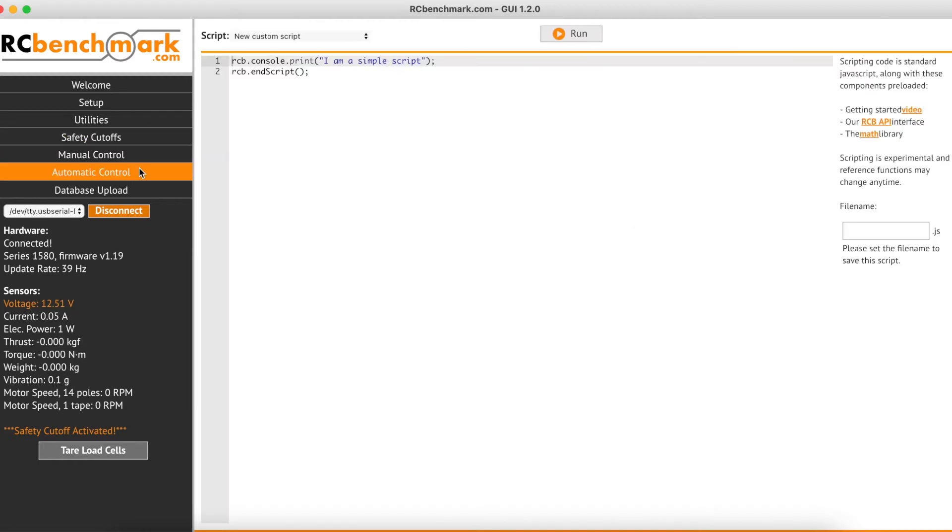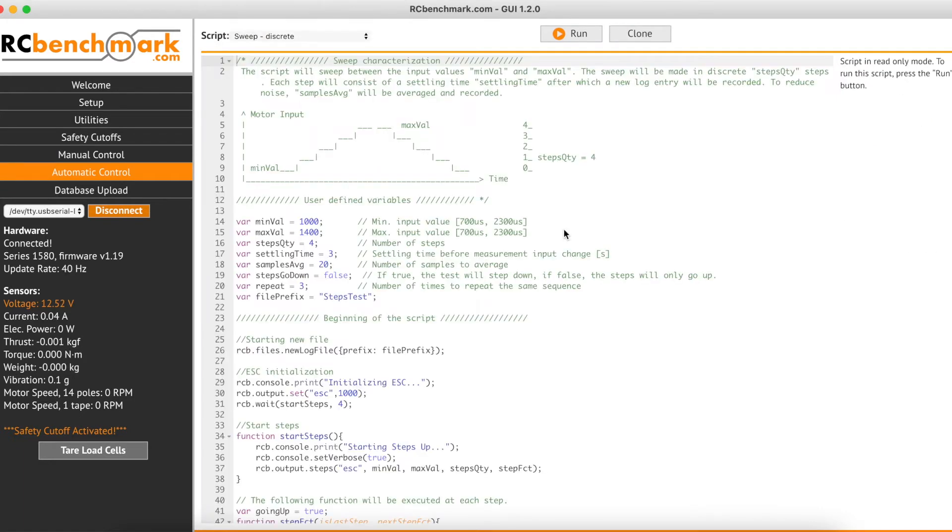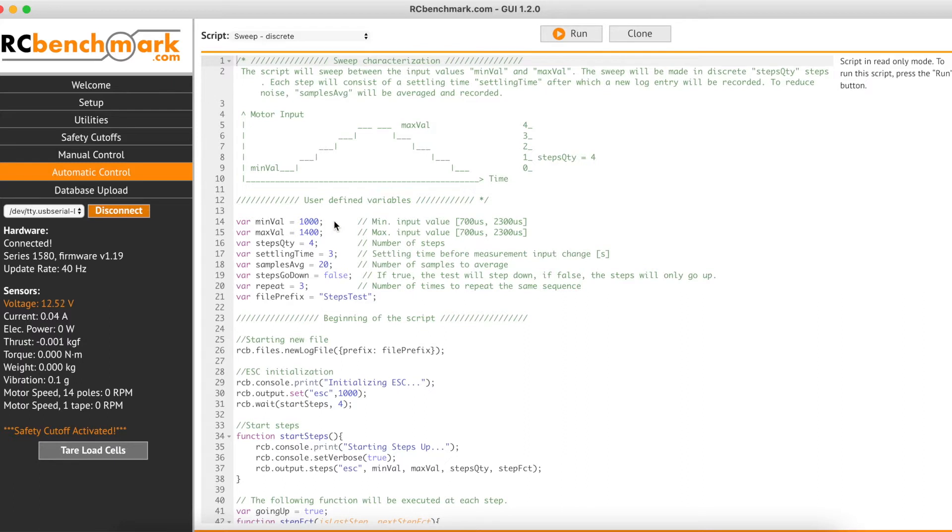Then we'll click on Automatic Control and select Sweep Discrete from the drop-down Script menu. Now the script itself contains lots of useful information for setting up your test. Here you can set the minimum throttle input value as well as the maximum. You can choose how many steps you'd like to cover between that min and max value, your settling time at each step before a measurement is recorded.